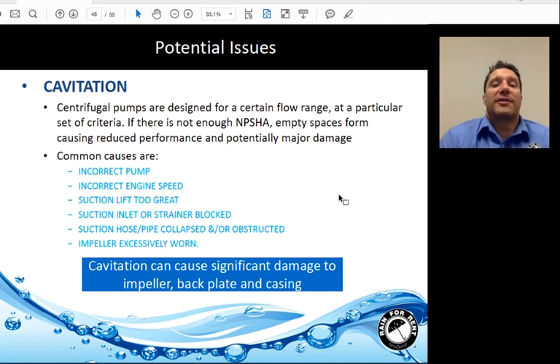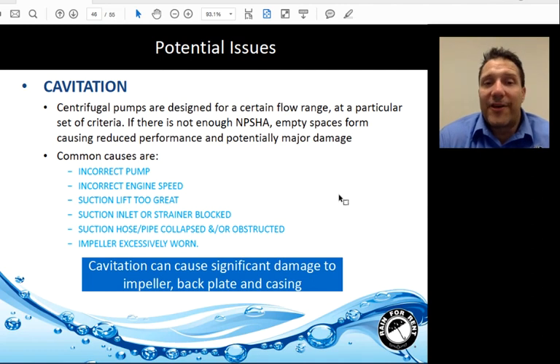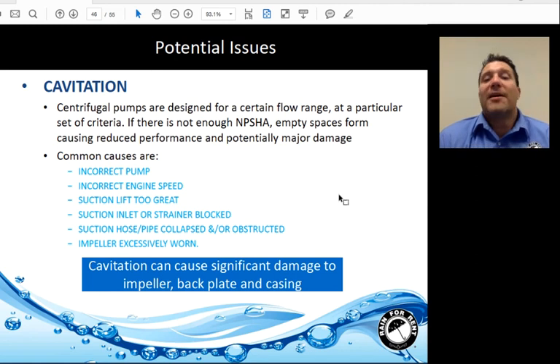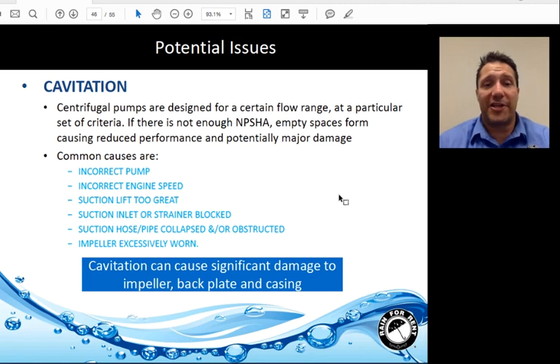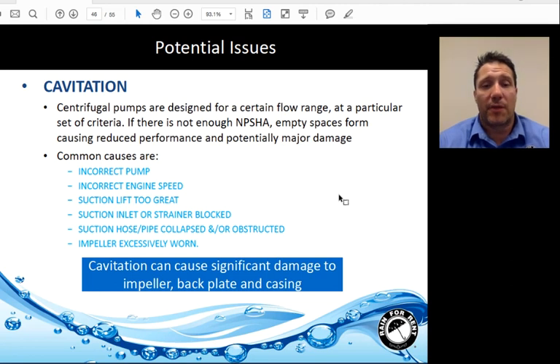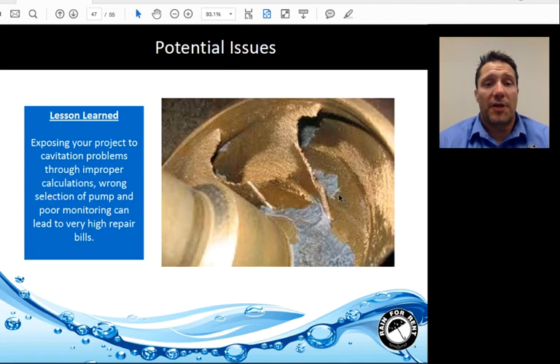Cavitation: Centrifugal pumps are designed for a certain flow range at particular criteria. If there's not enough net positive suction head available, empty space forms — essentially little bubbles of vapor or gas — causing reduced performance and potential major damage. Common causes include an incorrect pump design, suction lift too great for the pump, a collapsed or blocked suction inlet or strainer, or an excessively worn impeller. Cavitation can cause significant damage to the impeller, backplate, and casing, and can cause complete system failure. Improper calculations, wrong pump selection, and poor monitoring can lead to very high repair bills.